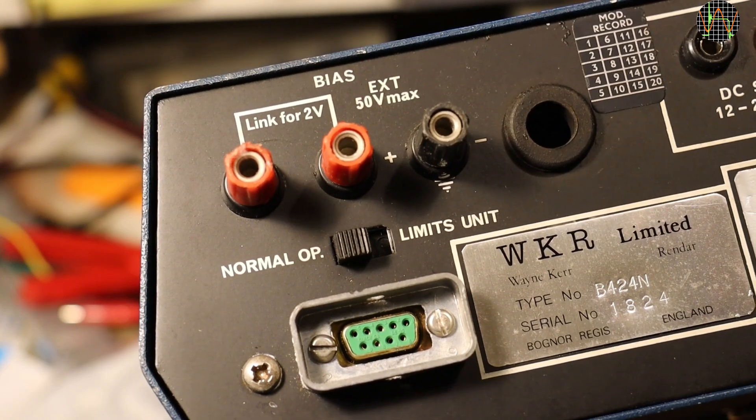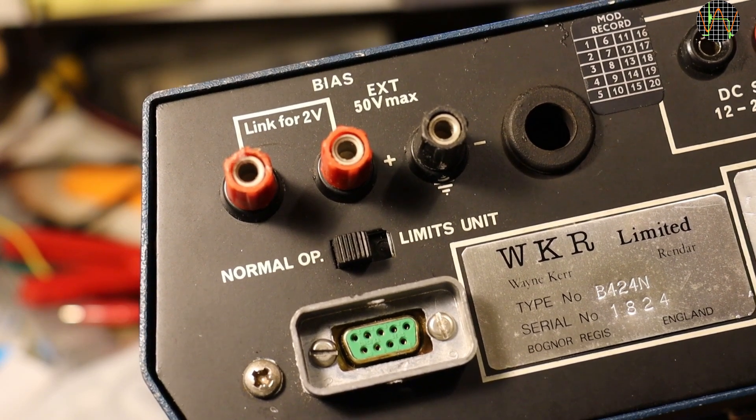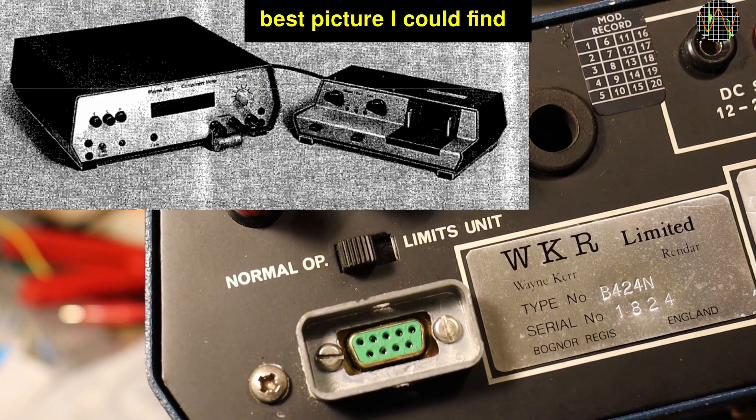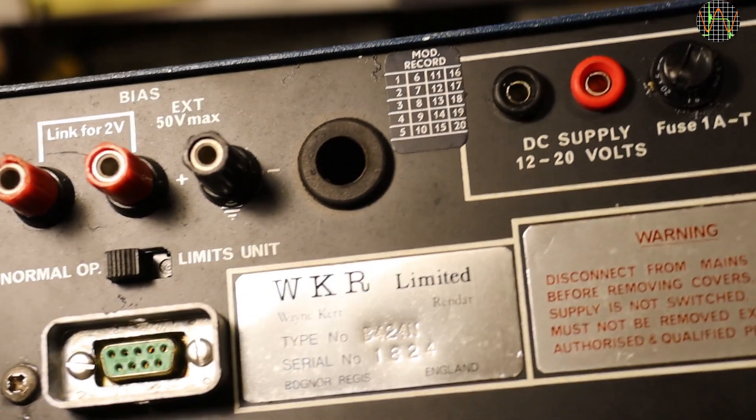There is a switch between normal operations and a limits unit. The limits unit was an optional add-on device which allowed setting of an upper and lower limit and would alert if a tested component was within or without. I don't have a limits unit, but if I had it would connect to the 9-pin socket.